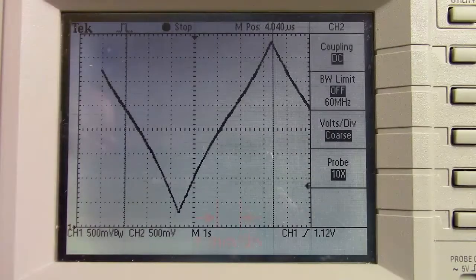The scale corresponds to one millimeter per division, and each step is four microns, which is visible on the oscilloscope. It's remarkably linear over the quarter inch travel, and it can be calibrated if you need more linearity.